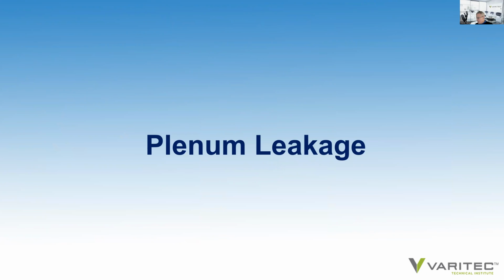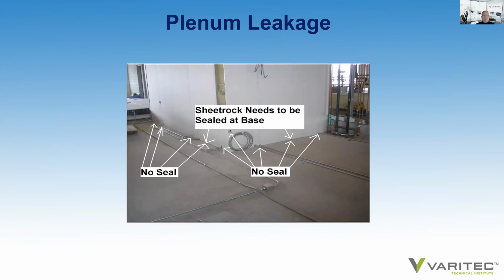So closing, we want to cover one of the biggest concerns of UFAD system, and that's plenum leakage. And this is one of the topics that has really challenged projects. I've installed a number of these systems, and unless leakage is addressed properly under the plenum, then it is very difficult to control plenum pressurization under the floor.